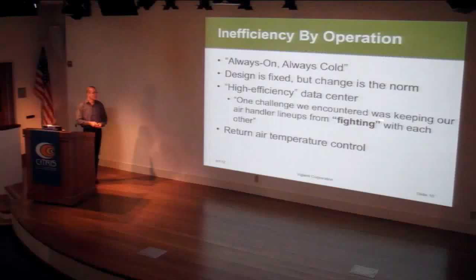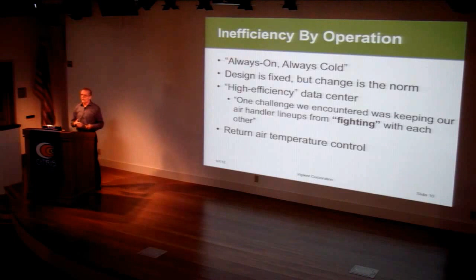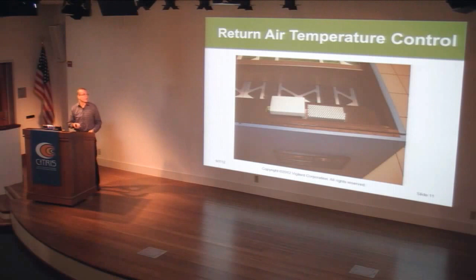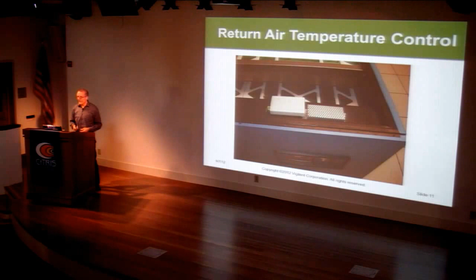The normal, almost overwhelming control strategy is simply return air temperature control of the air conditioners, like the ones I showed in the photos earlier. You saw that blue box - it has a temperature sensor on top that senses the temperature of the air being drawn in. This is a downflow unit: it draws air from above, down through the unit, through filters, into a cooling coil below, then discharges it into the raised floor so it disperses throughout the data center. That sensor connects to controls down here, where you can set what temperature you want at that point, with a simple feedback loop. It's a completely decentralized, often not even networked, control strategy. The reason is it makes it very easy to just plunk these units down wherever somebody thinks they need more cooling, without really thinking about the control operation of the facility.